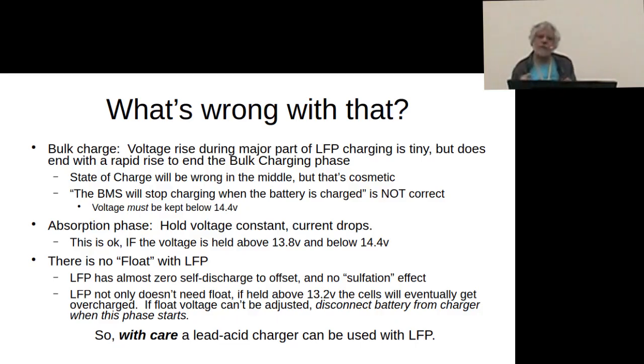Then there's the float phase at the end where it goes to 13.8. 13.8 is a magic number for lead acid batteries, and it's also a magic number for lithium, but for a very different reason. 13.8 is not the voltage a lithium battery wants to sit at—it wants about 13.2 to 13.4. If you keep putting 13.8 into it, it'll keep charging, the BMS won't do a voltage-dependent interruption, and you'll overcharge your cells. It'll take a while, but you'll ruin your battery. So if you can't adjust the float voltage on your charger, disconnect the battery and you can get by with it.